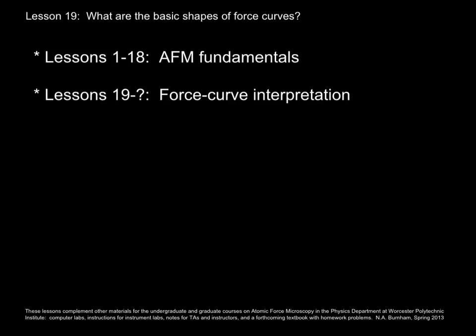So first of all, what do I mean by force curves? Well, you stop imaging, you stop the raster motion in X and Y, and instead you bring the tip and sample together by changing the height of the scanner in Z, and you watch the subsequent deflection of the cantilever, which is proportional to the force.